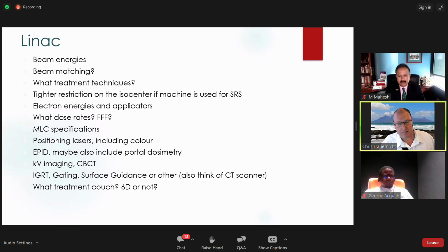Look at electron energies and applicators. So for our last installation, it turns out we never treated a 25 centimeter electron applicator in 20 years. So we just left it out of the specifications. What dose rates, flattening filter free, that seems to be fairly standard now. You may or may not have to specify a little more around the multi-leaf collimator. We specify the lasers that we want, the positioning lasers. And in particular, we specify the color. We just found that the red laser is not visible as nicely on dark skin. Green or blue is substantially better. So that's what we ask for.